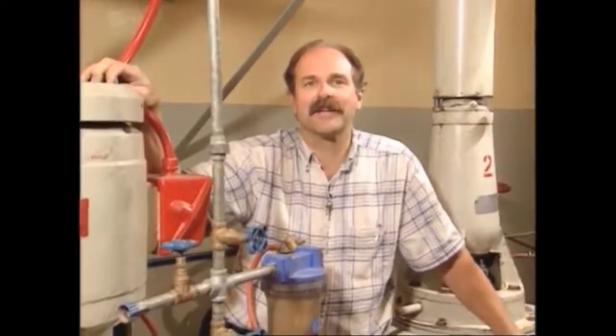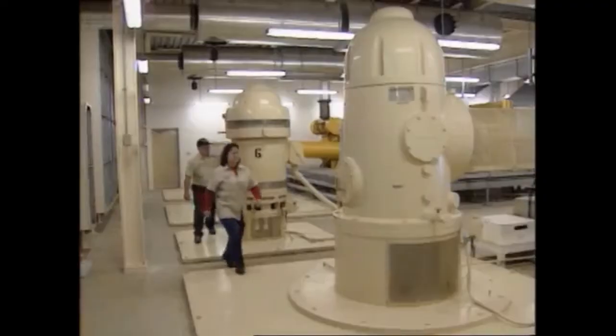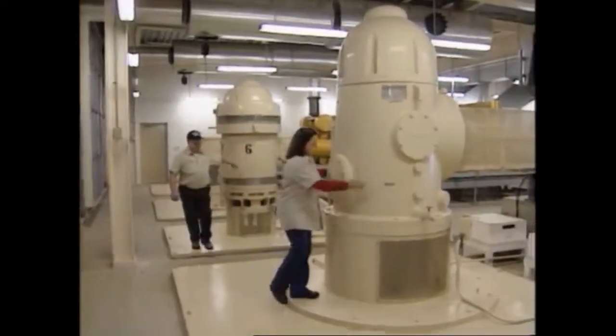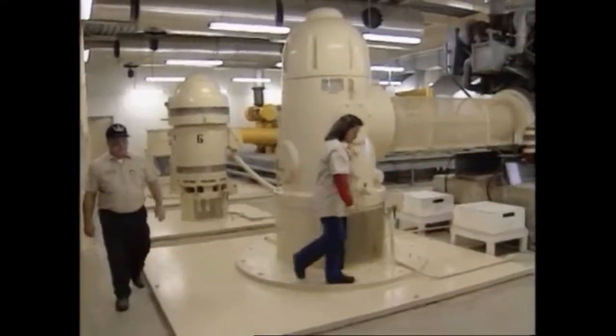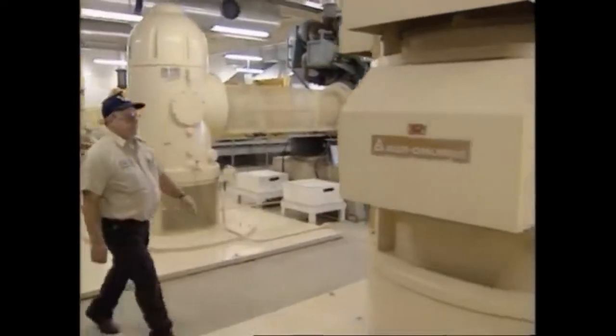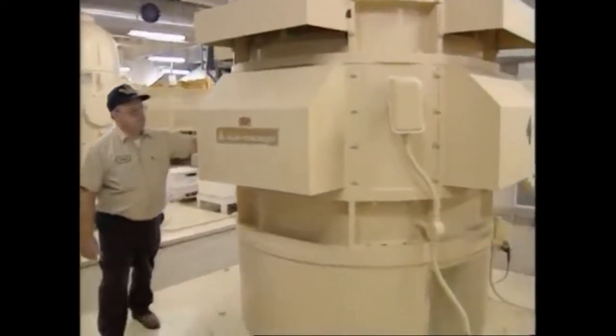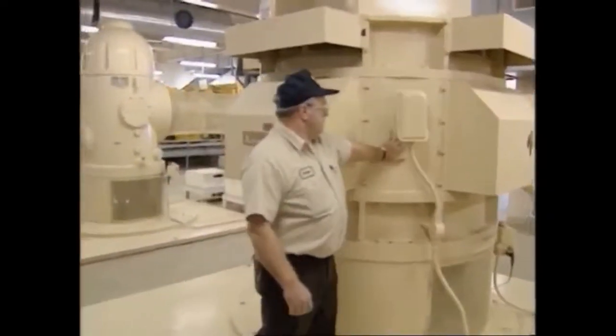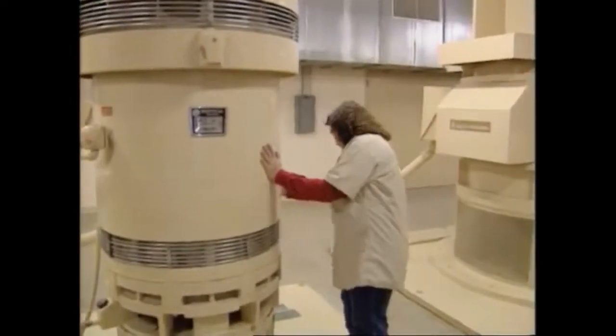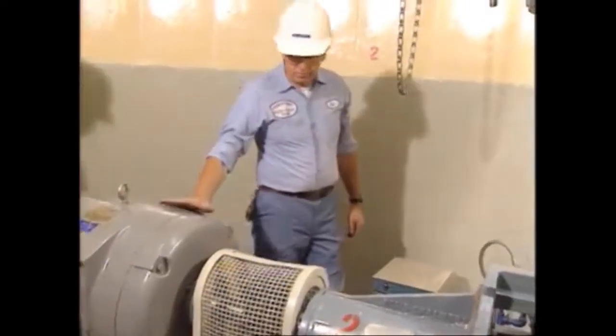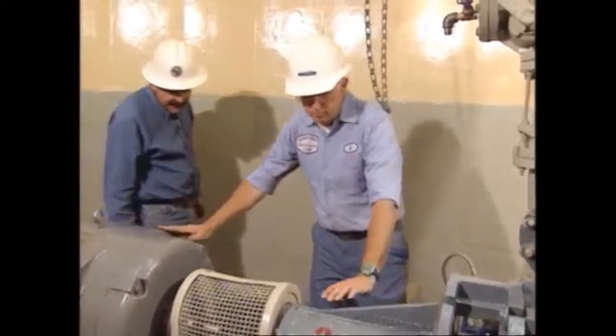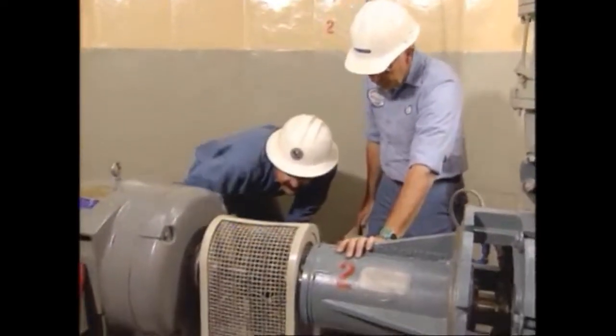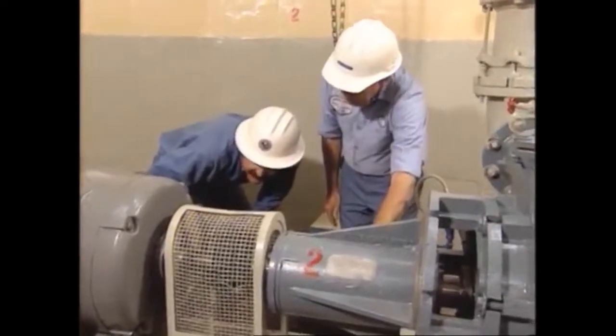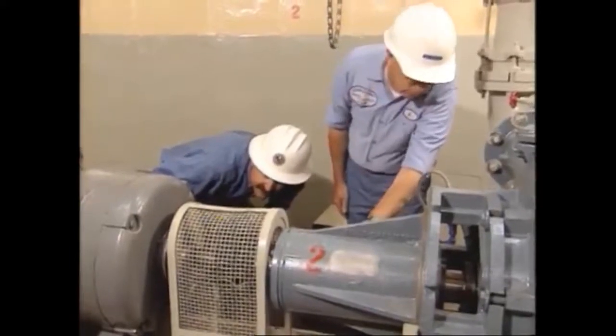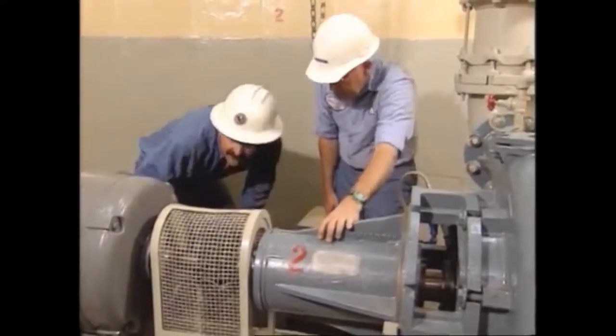The temperature rating consists of three components: the air temperature where the motor is operating, called the ambient operating temperature; the temperature rise, that's the maximum inside temperature of the windings during normal operation; and the hot spot allowance. Hot spots are present in every motor because of inconsistencies in the manufacturing process and in the winding materials, so a 10-degree centigrade or 20-degree Fahrenheit hot spot allowance is included.